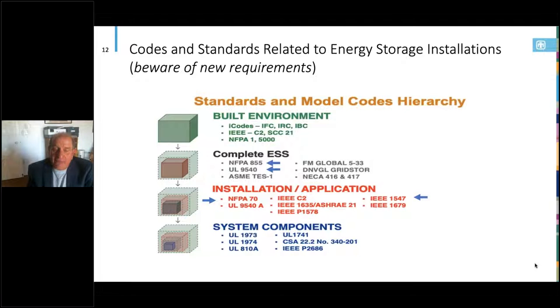They also have an impact on where you can locate the energy storage system. In other words, if you don't have this type of testing, then you have to put your energy storage system further away from any occupied buildings, etc. So they're very important - we're actually working a couple projects where they wanted to install the system next to the building, but they weren't UL 9540 compliant, and were told, no, you can't do that, you have to move it 100 foot away from the building. And that causes a problem, especially if you already have the infrastructure, the pad poured, the conduits in place, and you know where your point of connection is.